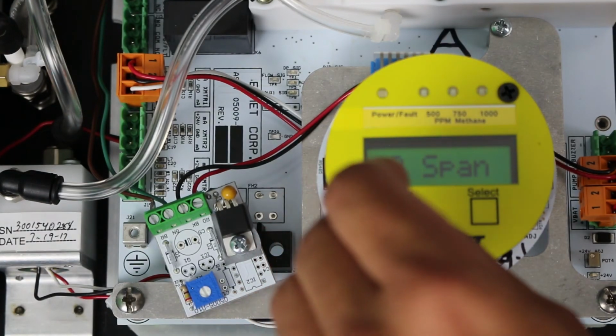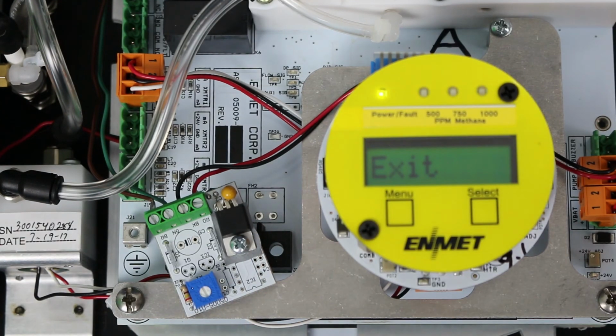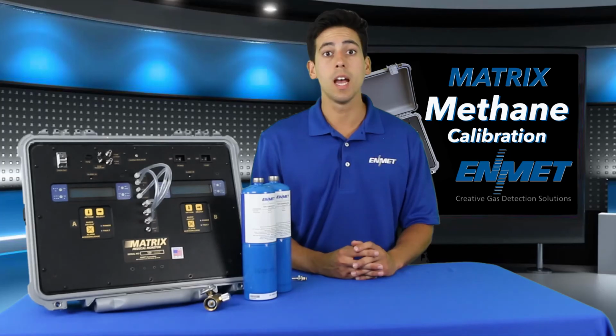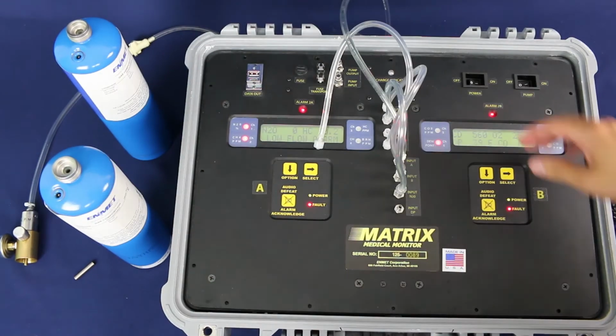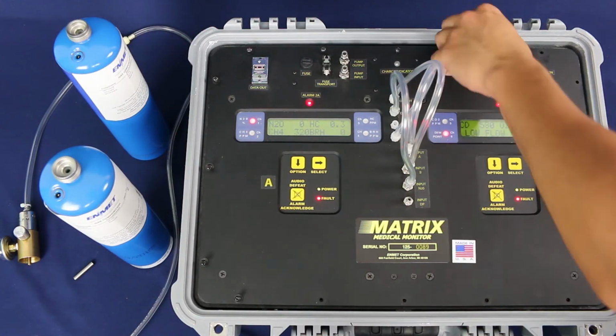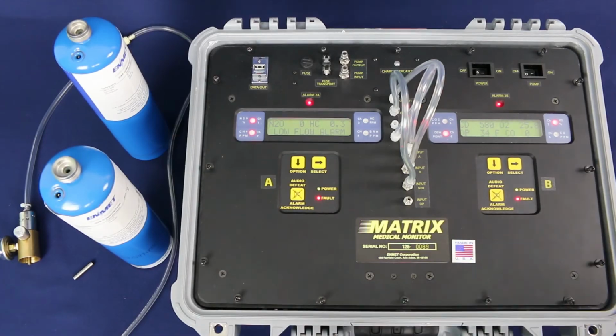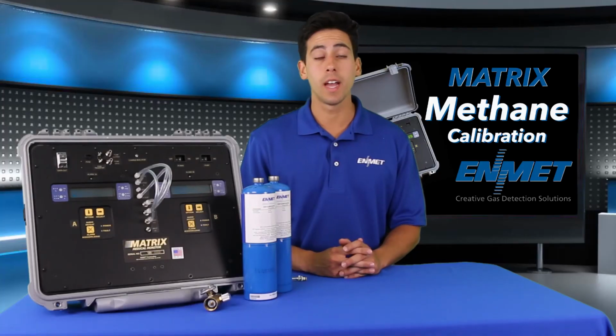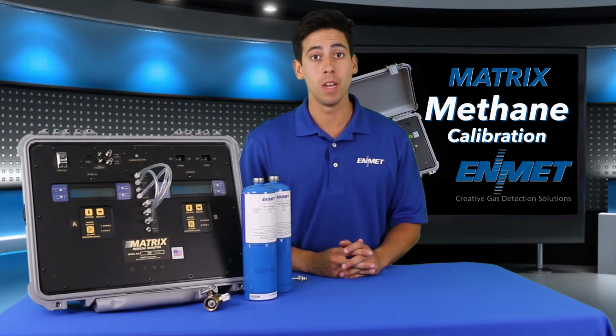Use the menu key to cycle through the maintenance menu options until you see Exit displayed. Then, press the select key to exit the maintenance menu and return to the operational mode. Now, you may flip the panel back over and reinstall the 16 panel mount screws. This completes the methane channel calibration for ENMET's matrix unit.